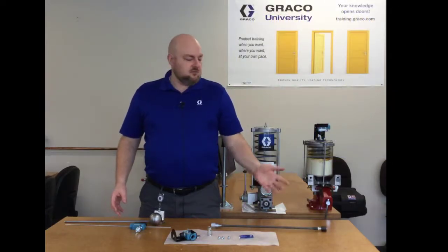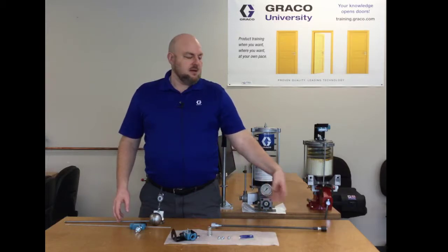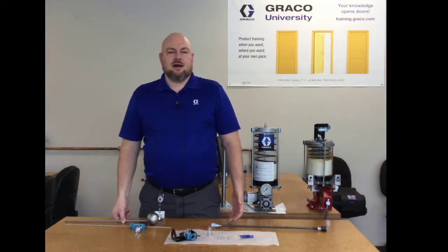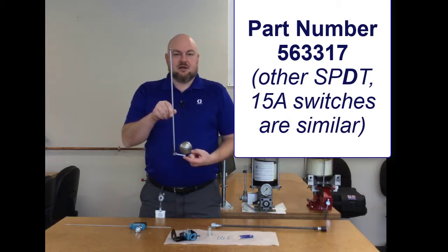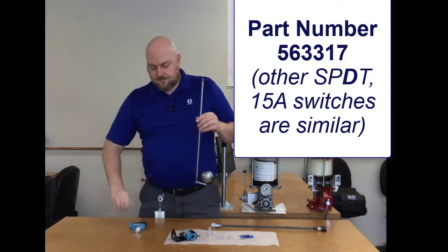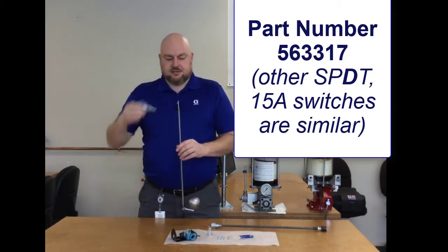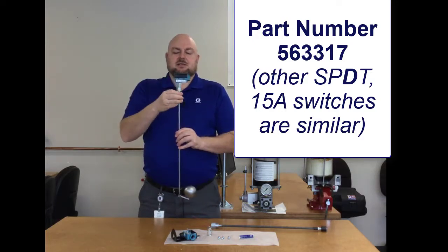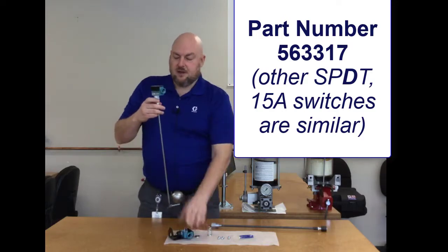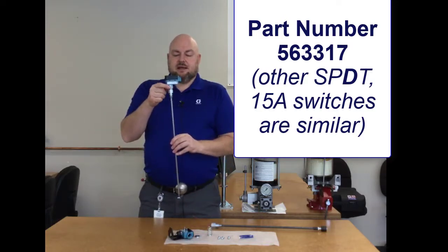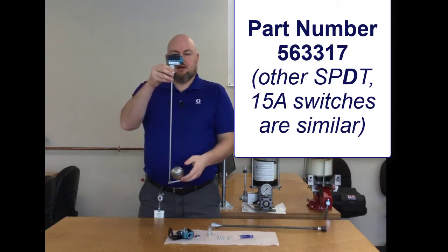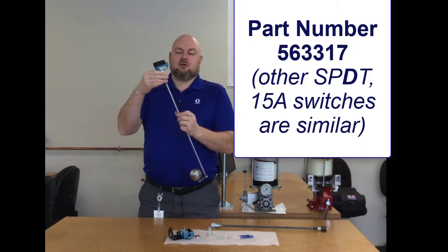If you are using an oil that doesn't work with the switch, if it's a real stringy oil or something else that gums up the low level switch but the pump still works, then there's another option available which people refer to as the toilet float because the way it works kind of resembles that float inside of your toilet. This one has a rod inside that goes in there and then the rod goes up inside this switch, and this is another one of these micro switches. It's similar to all these other switches that we use for cycle counting or like this one for the grease low level, but it has a little bit of a different end on it here because instead of that rubber boot there's a threaded piece to receive this. All this does is move up and down to flip the switch. This is again 1¼ inch thread because it's going to install on that same port on the cover of the oil reservoir.